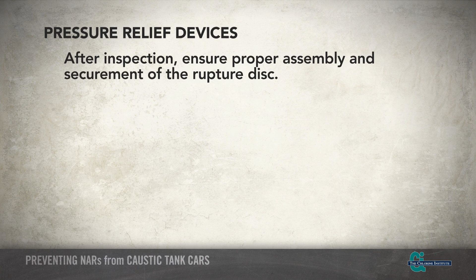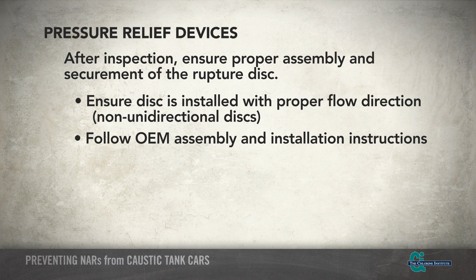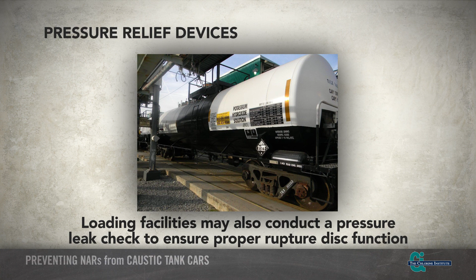After inspection, it is crucial to ensure proper assembly and securement of the rupture disc assembly. Be sure the disc is installed with proper flow direction. Original equipment manufacturers, or OEMs, provide instructions to ensure proper orientation of the disc and housing assembly. Loading facilities may also conduct a pressure leak check to ensure proper functioning of the rupture disc in addition to removing the disc for visual inspection.